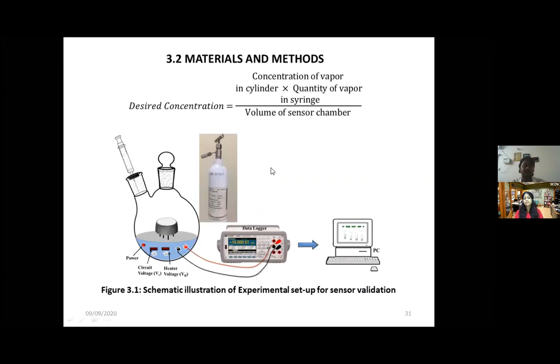So the first one is IV characteristics. We really wanted to ensure that the coated sensor material, the substrate and the gold electrodes are intact. What if it comes out? So for ensuring that, we go for IV characteristics. We performed the IV characteristics at 200 degrees Celsius with a voltage ranging from -5 to +5. We observed a linear response, which tells us this is ohmic. So an ohmic response, that is a linear response, indicates that the electrode, sensor material and the substrate are in good contact.